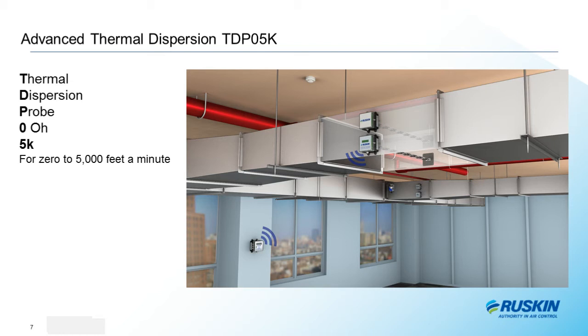Well, we have some. We have 8 sensing points per probe and up to 16 probes per air measurement station. What that means is that we can sample the air in more places in the duct and arrive at a more accurate air measurement. Using more sensing points per air measurement station makes any bad location better. We do have a limit of 128 sensing points for very large or very bad installations.